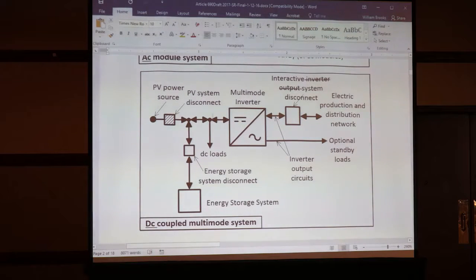All right, so typically, and as we see here at the expo, when you have multiple inputs, you're going to want to have the disconnecting means for all of those inputs very close to your multimode inverter, because the code requires you to be able to de-energize all energy sources into a piece of equipment, and it has to be within sight or at the equipment. So you can't have a PV system disconnect that's 100 yards from your multimode inverter and say, hey, I got one out there. That's not acceptable. It's got to be at the inverter where you might have to work on the piece of equipment, which is why we have some great pieces of equipment that we've been using for years that do this kind of stuff every day.